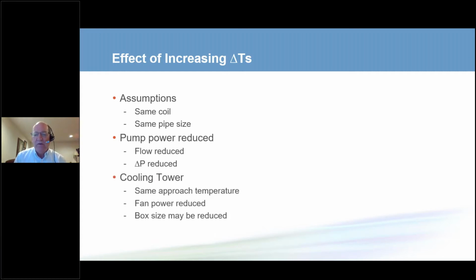For the cooling tower, we're going to resize that cooling tower using the same approach temperature. That is the same temperature difference between the leaving tower temperature and the outside air wet bulb temperature. When we do that and we've reduced the flow rate, the water temperature going to the cooling tower is higher, and therefore the cooling tower is a more effective heat exchanger. We can select a cooling tower that's usually about 7 to 10% lower cost and lower fan horsepower.